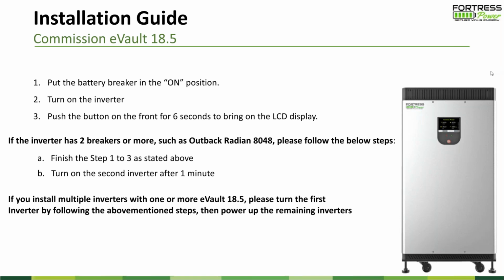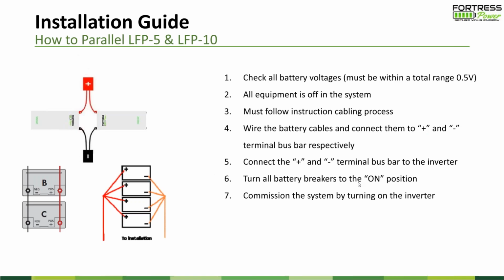And on the next slide, I'm going to discuss a little bit how to parallel the system. For the LFP-5 and LFP-10, we allow the customer to parallel 2 battery banks in the system. We do recommend 2 ways to do it. You can do DC chain. If you do DC chain, make sure you pull the power from both sides, positive from one side, negative from the other side. Just don't try to pull the power from one side. It's going to put a lot of pressure on one battery and less pressure on the other battery. After 1,000 cycles, you will see the differences in the capacity deteriorating.